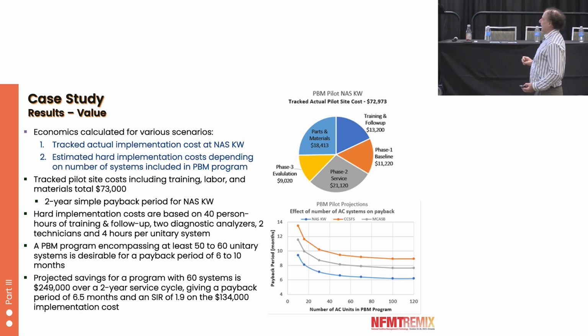We estimated that with 40 hours of training, 2 analyzers, and 2 technicians at each unit for 4 hours once a year, we'd get a payback period of 6 to 10 months. This is also increasing the amount of units in the program to about 50 or 60, which for DoD is not a problem because they have hundreds of units, a couple hundred at each base. Most people might not have 50 or 60 DX equipment units, depends how big your facility is. This is based on 12 tons average, so if you have, say, fewer 30-ton units, that's also going to work.